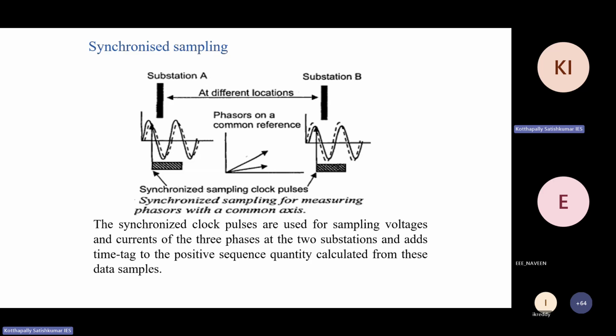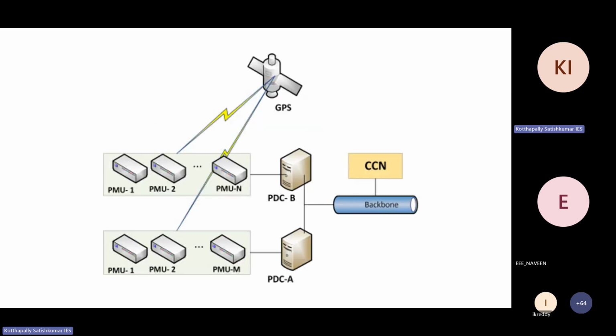Each measurement will have a time stamp. For example, if the time is 7:53, the PMU measuring voltage and current will measure the amplitude and angle, and stamp the data with the time, such as 7 hours 54 minutes 30 seconds and 20 milliseconds. So every data point is stamped, and you can compare all the common time frames to get accurate data.